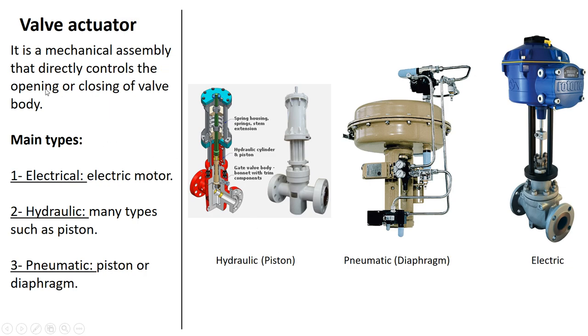The valve actuator is a mechanical assembly or device that directly controls the opening or closing of the valve body. It has three types: electrical, hydraulic, or pneumatic, depending on the type of power it uses. Hydraulic actuators, such as a piston type operated by hydraulic power, are very rare. The electrical one is more modern, but the most common is the pneumatic one, which uses air pressure signals.